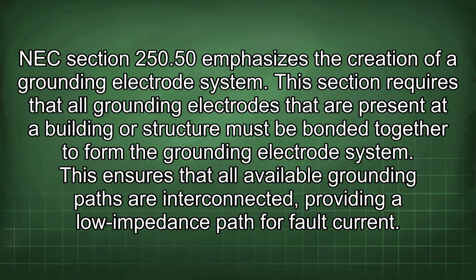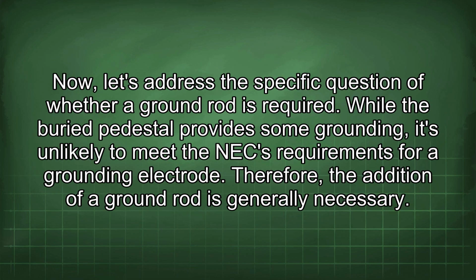NEC Section 250.50 emphasizes the creation of a grounding electrode system. This section requires that all grounding electrodes that are present at a building or structure must be bonded together to form the grounding electrode system. This ensures that all available grounding paths are interconnected, providing a low impedance path for fault current. Now, let's address the specific question of whether a ground rod is required. While the buried pedestal provides some grounding, it's unlikely to meet the NEC requirements for a grounding electrode. Therefore, the addition of a ground rod is generally necessary.